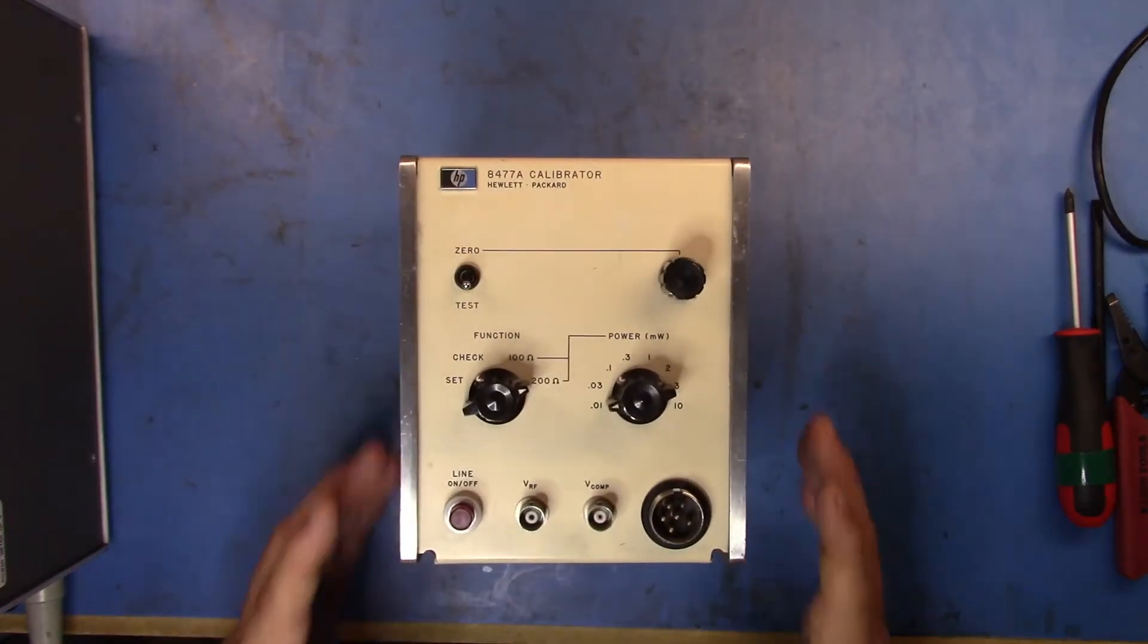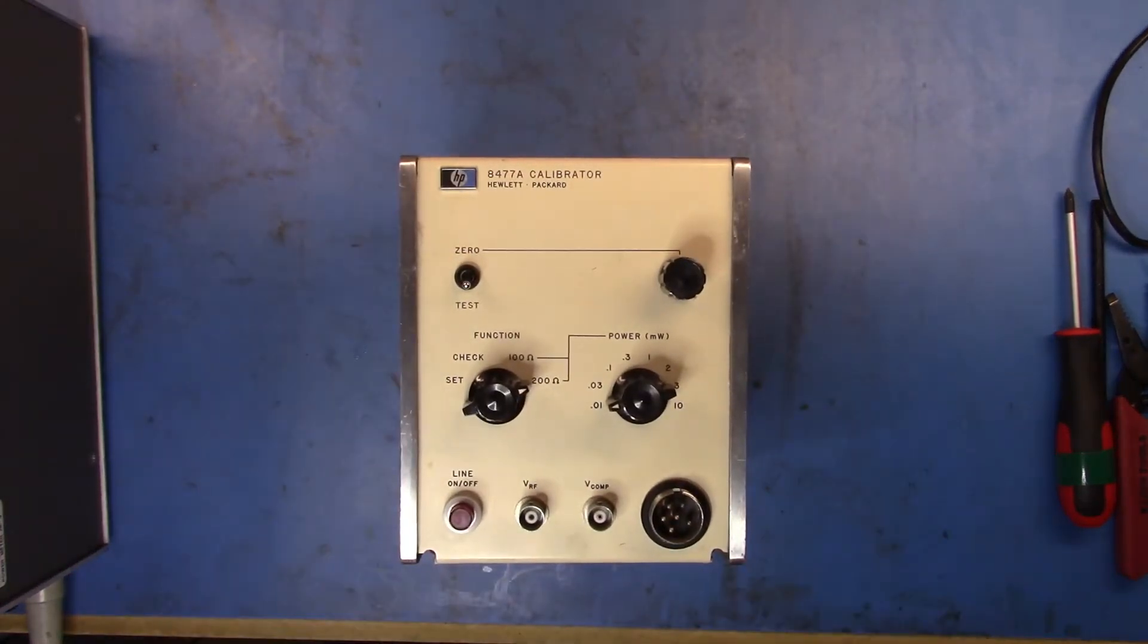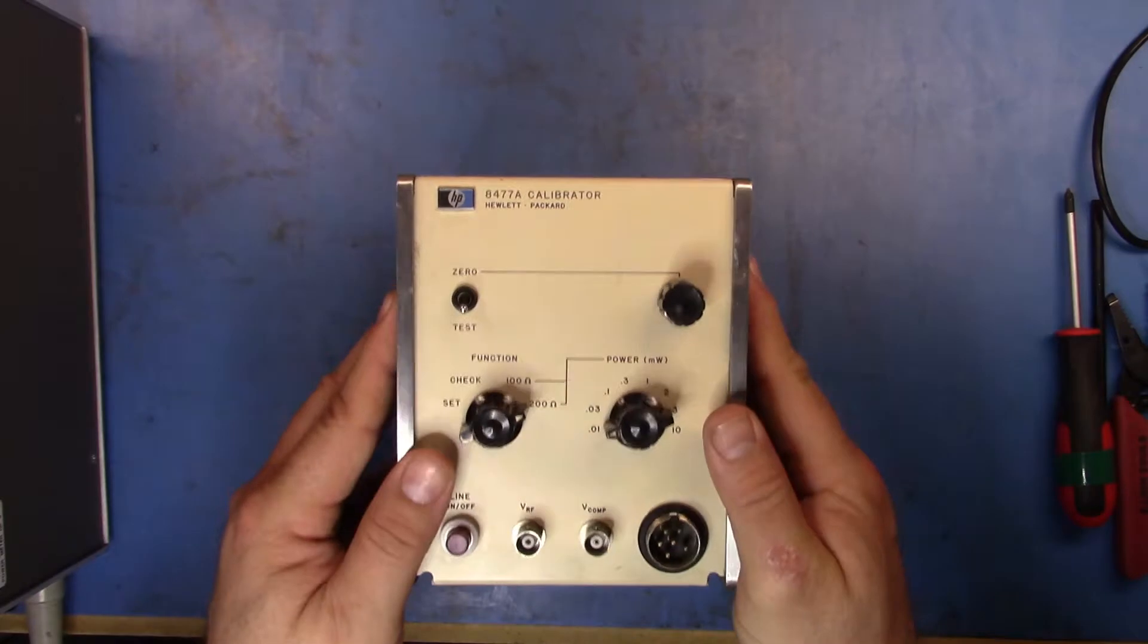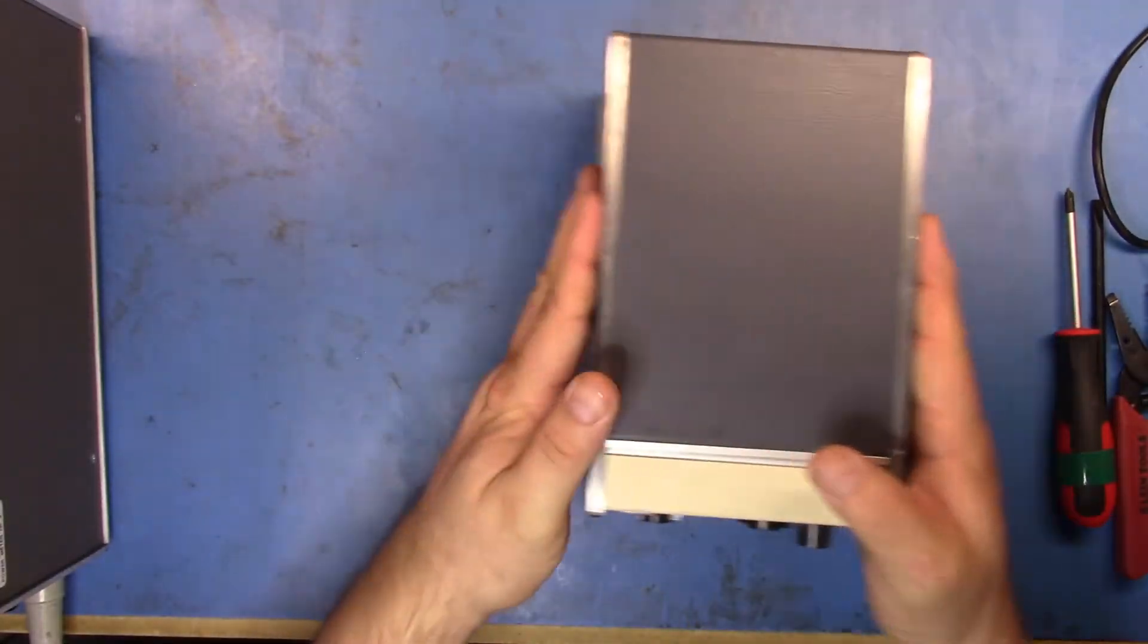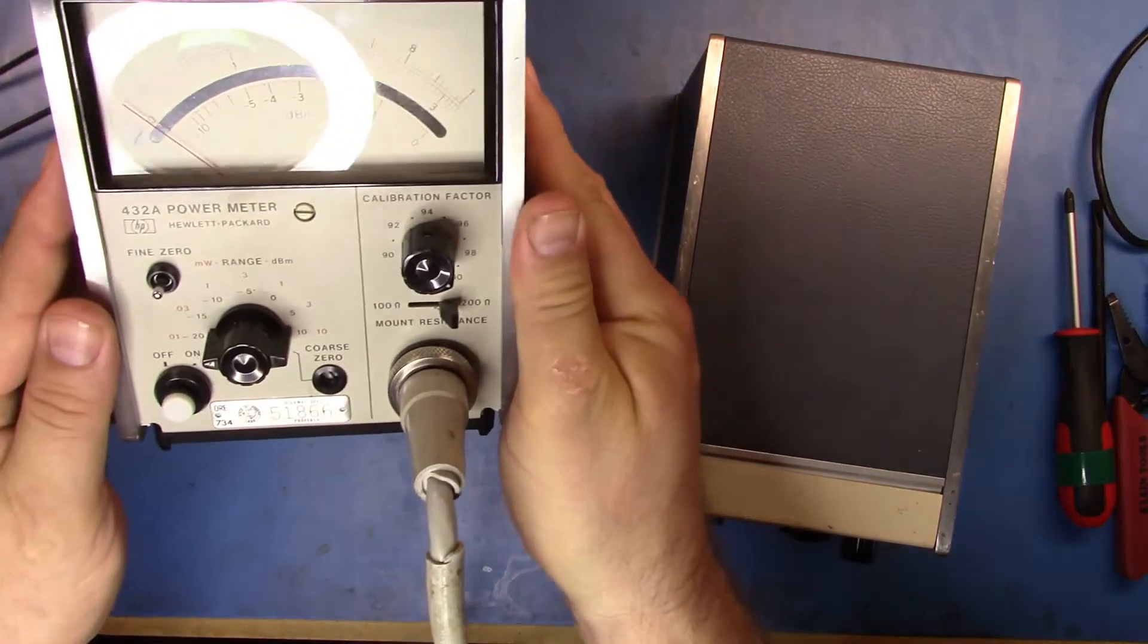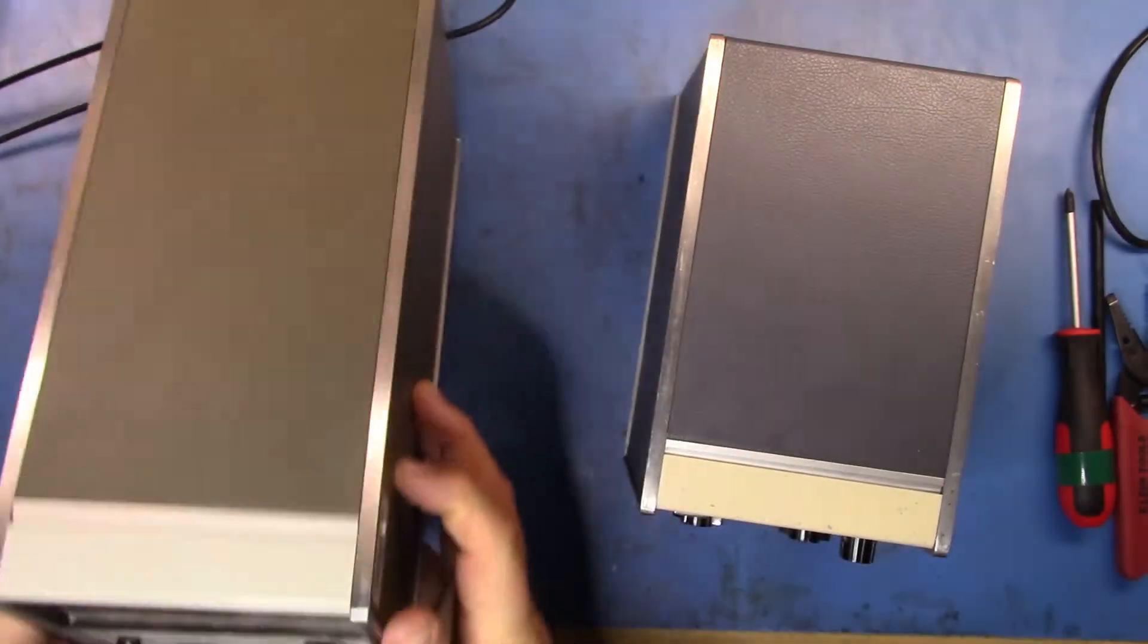Anyway, what is this piece of kit? It is an 8477A calibrator. It is designed specifically to help you calibrate power meters such as the 432A that we see here.